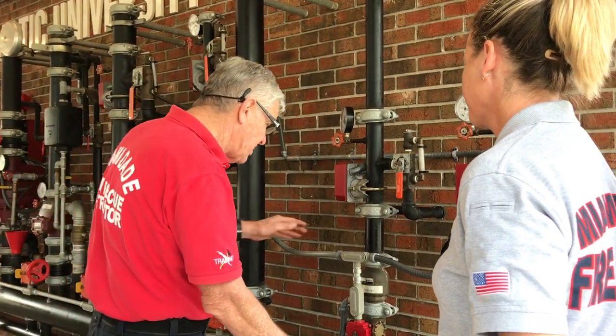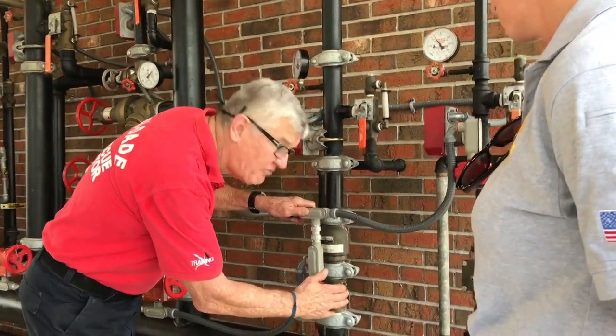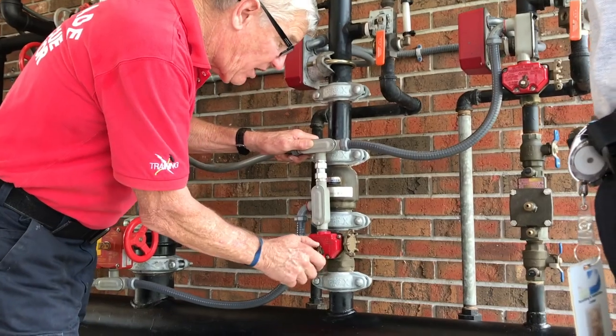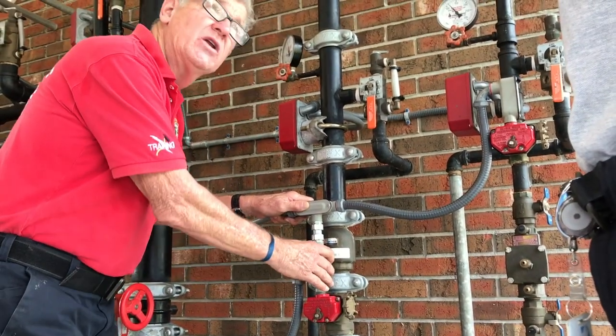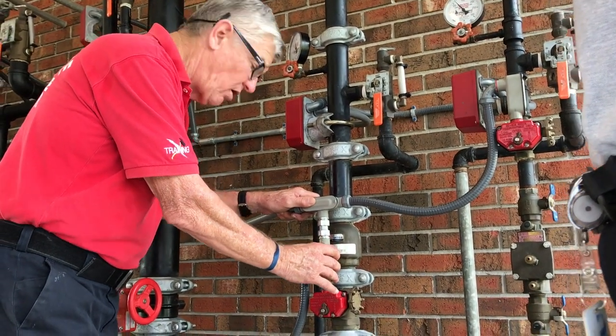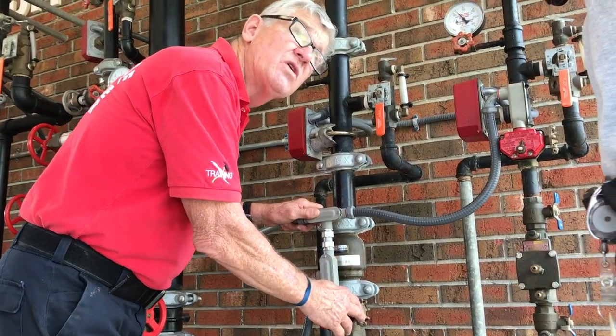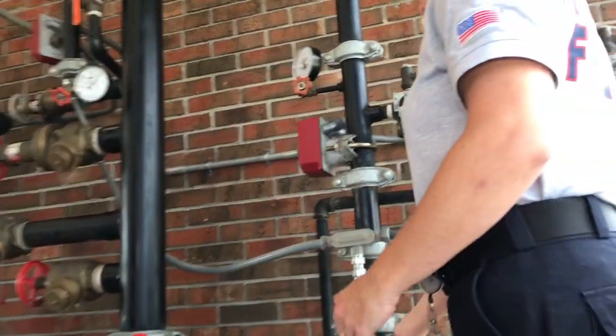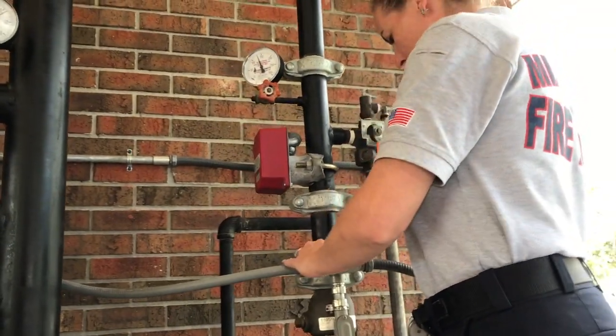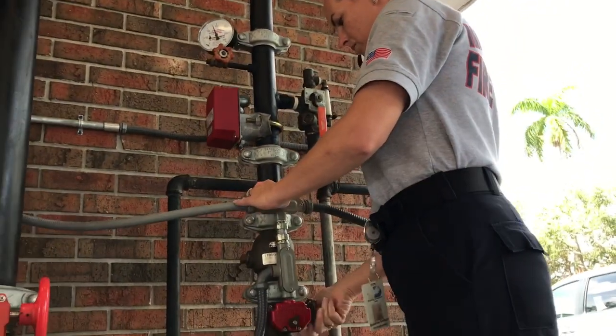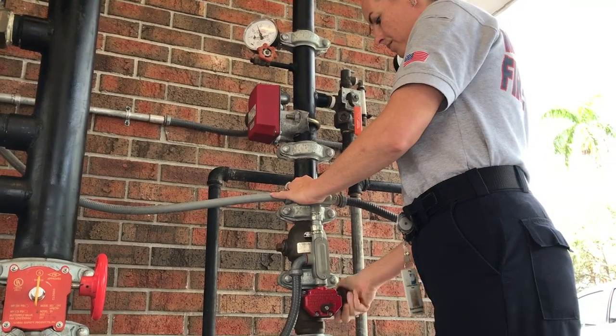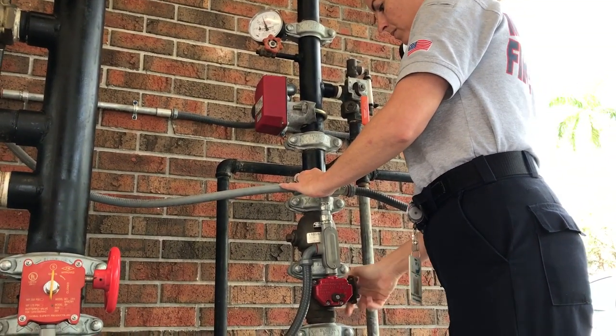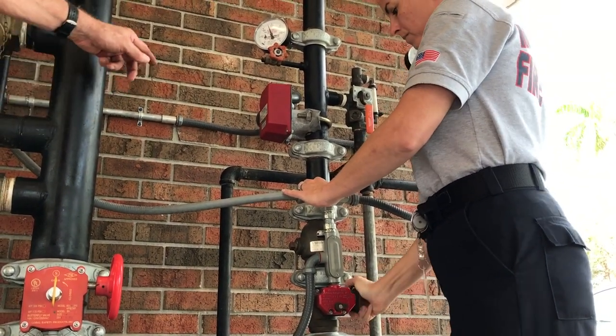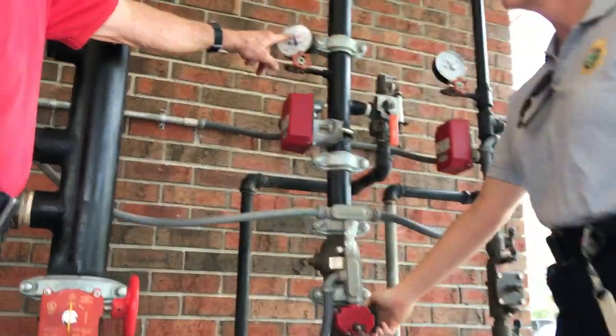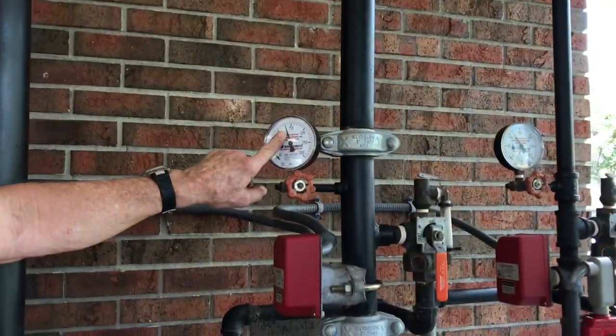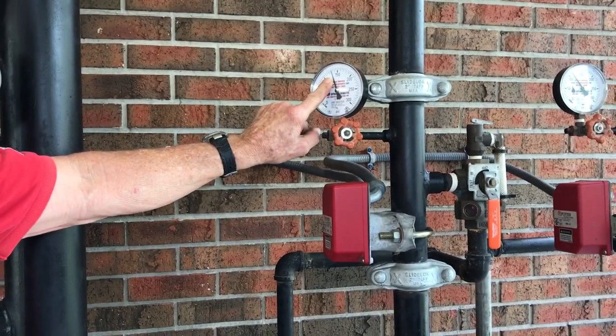And when you do, Susie, it's the same thing. You're going to shut off the control valve here. It'll indicate that it's closed and we'll initiate a tamper switch or supervisory alarm. So go ahead and shut that off. All right. So we see what we got. Yep. Of course, that would not be the case if there was actually a sprinkler flowing.